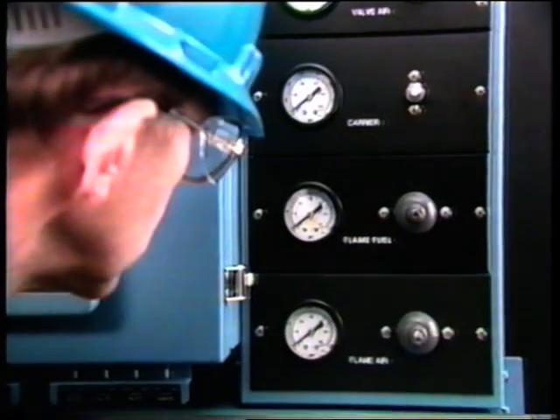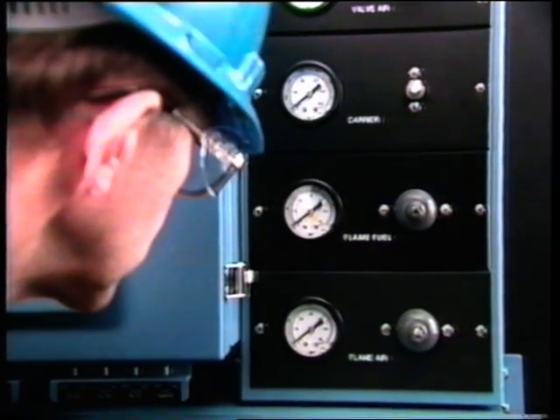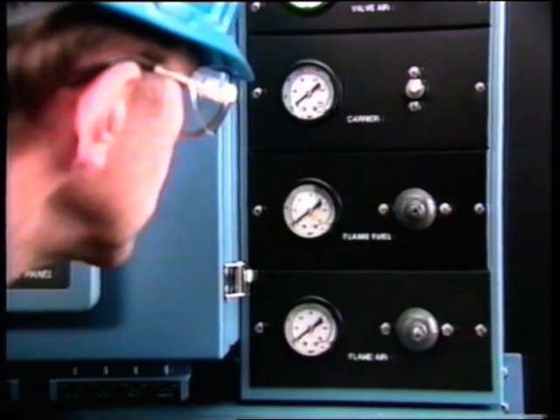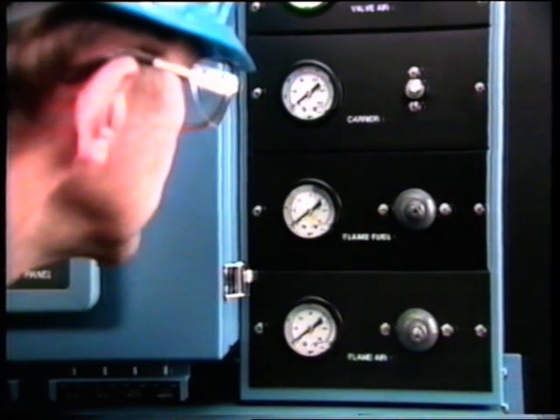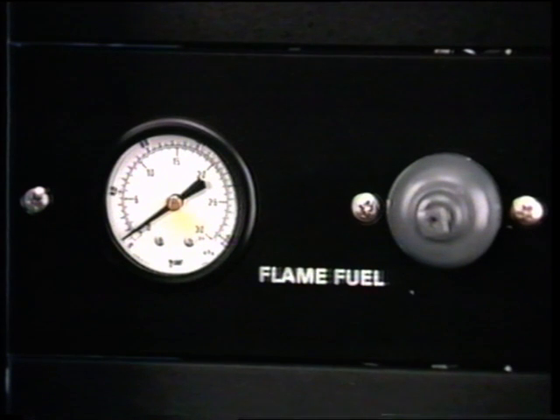To turn the flame off, turn the flame fuel regulator, the carrier regulator, and the flame air regulator all the way down. Because hydrogen burns with an invisible flame, it's very important that the pressures are at 0 to ensure the flame is out before you begin your maintenance.